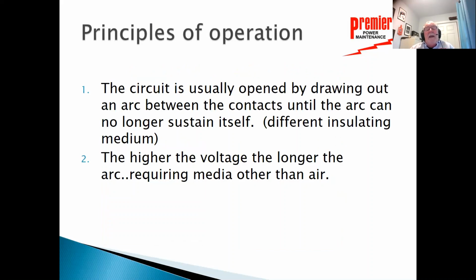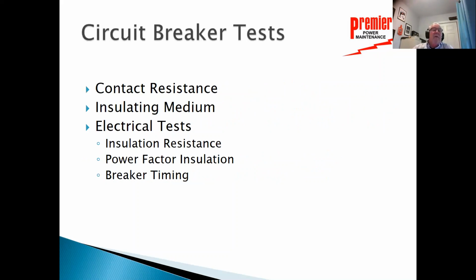Usually you have a drawing out of a large arc between contacts, okay? The higher the voltage, the higher the arc, which requires media other than air. So for circuit breaker tests, I always want to make sure the contacts are good, and to do that I have to do contact resistance. I want to make sure the insulating medium is good. It could be air, which I can't test, but if it's an oil circuit breaker, I can certainly test the oil. If it's a vacuum circuit breaker, I can do some tests on the vacuum. If it's an SF6 circuit breaker, I can do some tests on that SF6 gas.